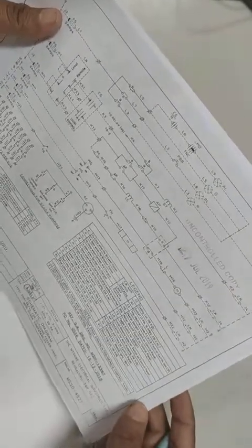Here, I can show you this is an 11 kV breaker control circuit. Likewise, CT circuits, metering circuit and protection circuits. This is the AC circuit and this is the protection circuit. So the first thing is we need to understand how to read a drawing and the fundamentals of troubleshooting the problems.